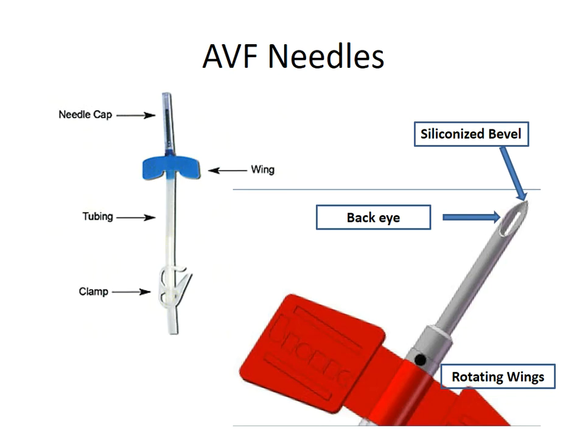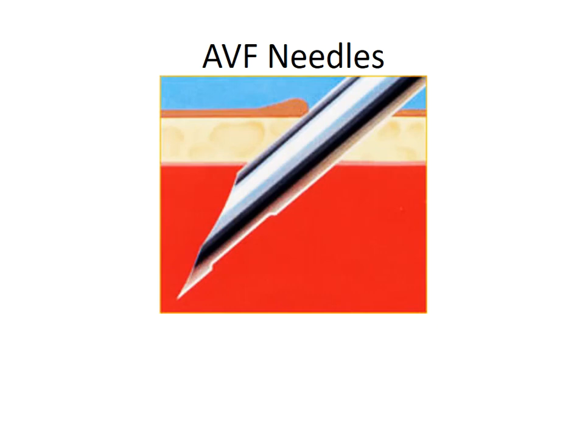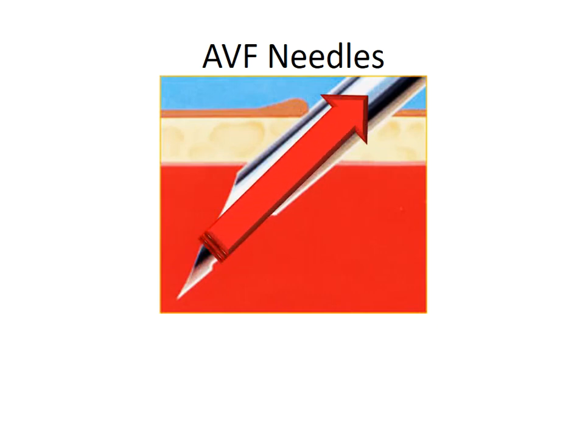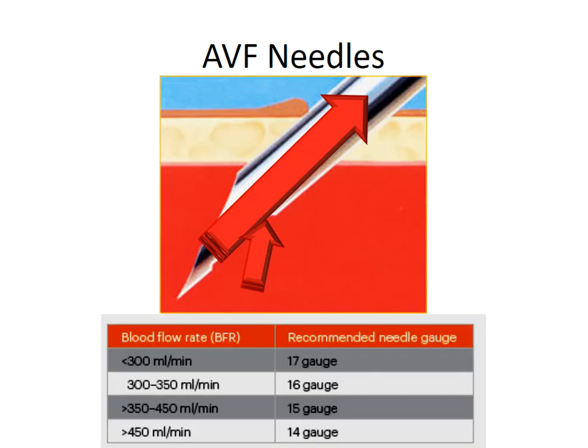The rotating wings help in repositioning the needle during dialysis. Blood can flow through the needle in both directions — from the bevel as well as from the back eye — according to the desired blood flow. You can match the needle size to the required flow: less than 300 mL/min uses a 17-gauge needle, more than 300 mL/min uses a 16-gauge, and above 400 mL/min requires a larger needle size.